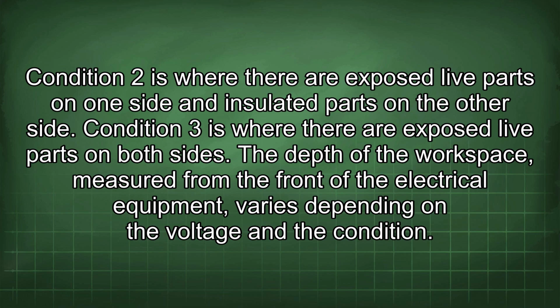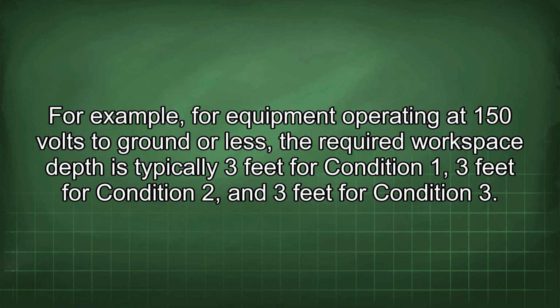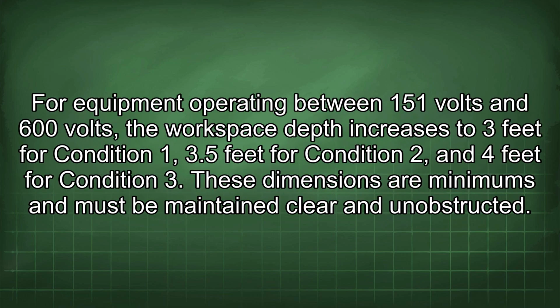The depth of the workspace, measured from the front of the electrical equipment, varies depending on the voltage and the condition. For example, for equipment operating at 150 volts to ground or less, the required workspace depth is typically 3 feet for condition 1, 3 feet for condition 2, and 3 feet for condition 3. For equipment operating between 151 volts and 600 volts, the workspace depth increases to 3 feet for condition 1, 3.5 feet for condition 2, and 4 feet for condition 3. These dimensions are minimums and must be maintained clear and unobstructed.